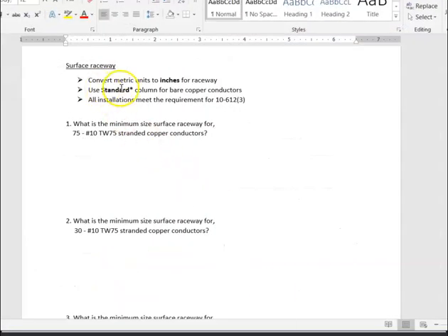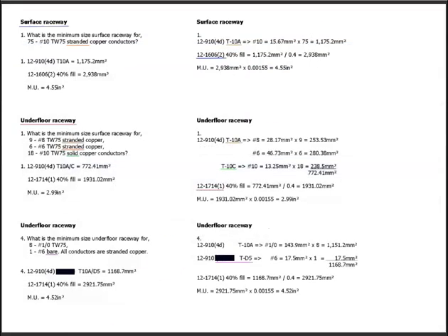So right here, table D5, that's where this is. And we're using the standard column. The first column is nominal. Here I'm just using standard. The standard column is just 1 over. So out of table D5, we just add them all up here. You can see the breakdown. 12-910, 4D, table 10A gives us our number 1 aughts. Add them up, there was 8. And then table D5 in the standard column, the number 6 is good for 17.5. There's only 1. We add them up, and again, this represents 40%.